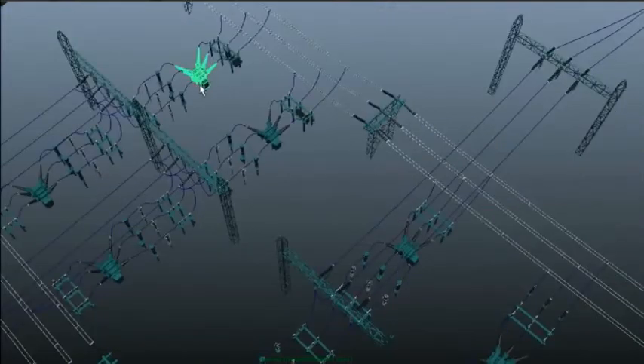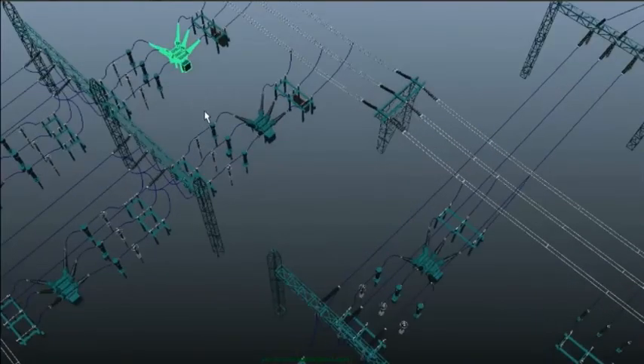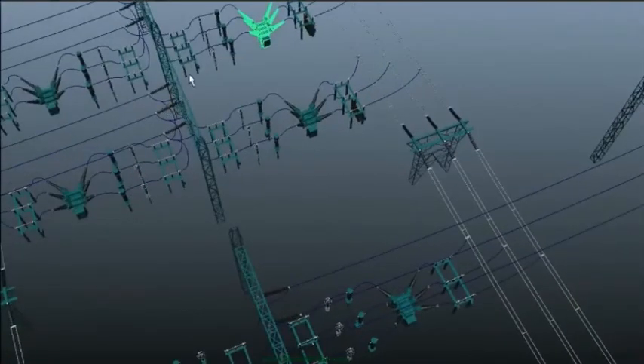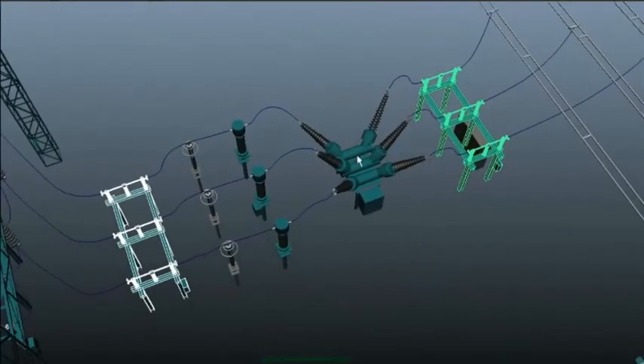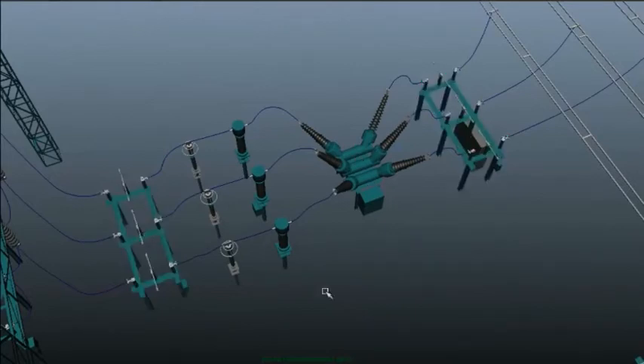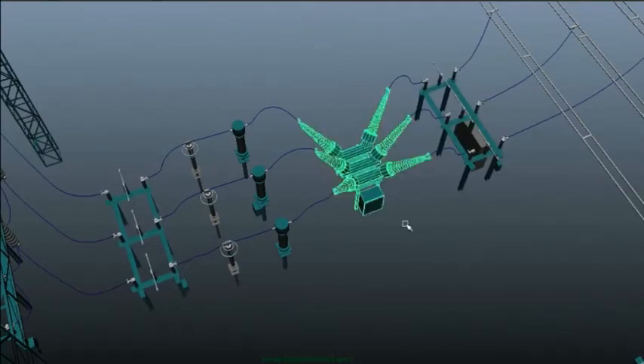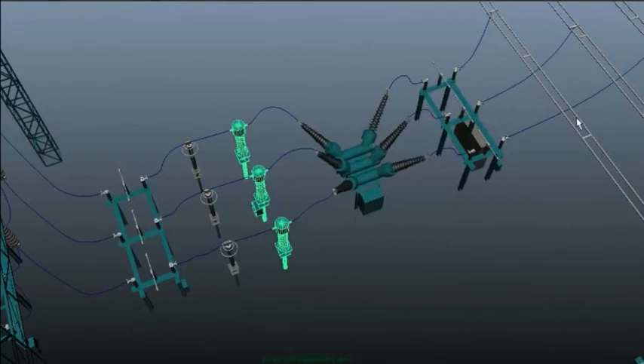During the time of maintenance, the circuit breaker must be isolated from the system properly, and for that we use isolators. Like, when the isolators are operated, their rods rotate like this, they become off. And now we can do work on the circuit breaker safely, though there is a charge on the bus. These terminals are connected to earth so that even after opening, the remaining electric charge in the breaker goes completely into the earth. Otherwise, the maintenance personnel could get a severe electric shock if they touch the circuit breaker.